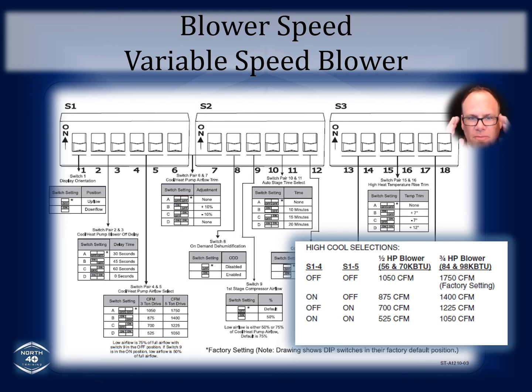And some people set these up and they say, well, how do I know that it's actually achieving that? Okay, well, here's a secret. These things are pre-programmed to achieve the CFM value that you set them at as long as you're less than 1 inch of static. So that control module that's on the end of that motor will maintain that 1050 CFMs on the off-off configuration for the half horsepower blower unless you go over 1 inch of static. Okay, so your measurement before the blower and after the blower has to be less than 1 inch of static in order to maintain that 1050.